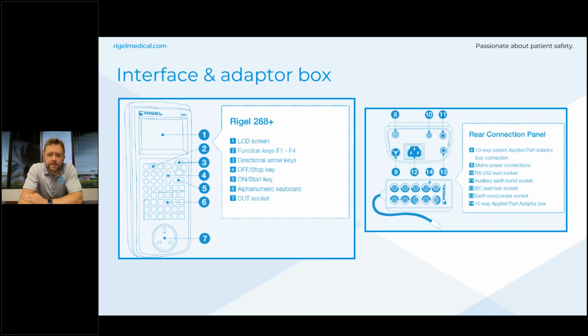So 11 and 13, these are your tests for the probes, so point-to-point or ground bonded enclosure leakages for the bottom one on its own. The 288 also incorporates an IEC lead test, and that checks the polarity, the continuity and the insulation of a lead. So it doesn't just test the medical device itself, but also the leads that come with it. And the way you do this is connect the lead to the front where the DUT socket is normally to this point here, and you'll be able to test all your leads that are in your facility.